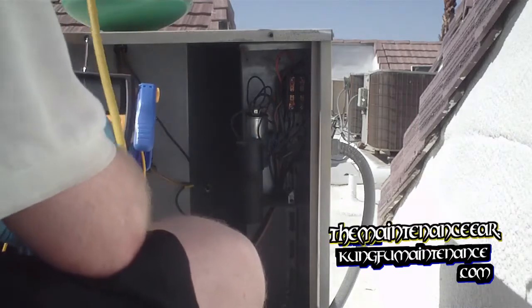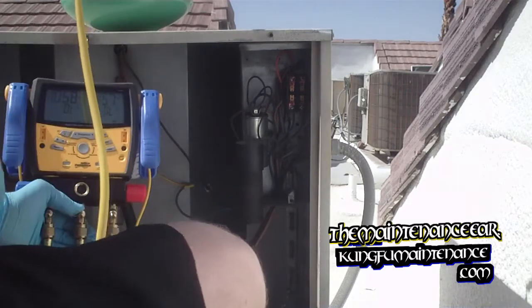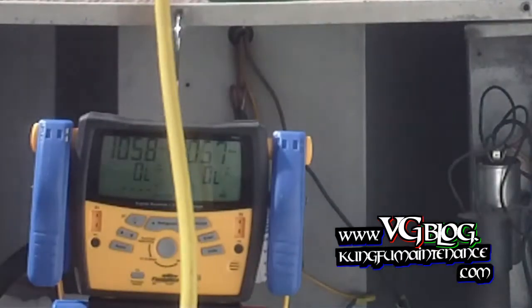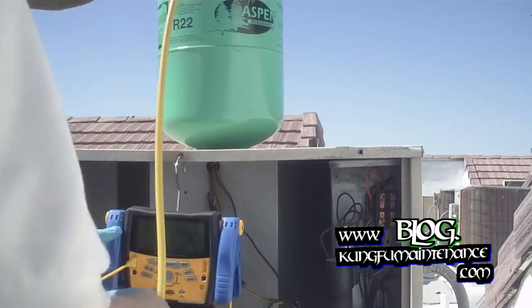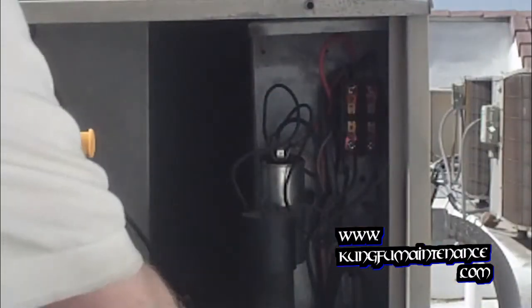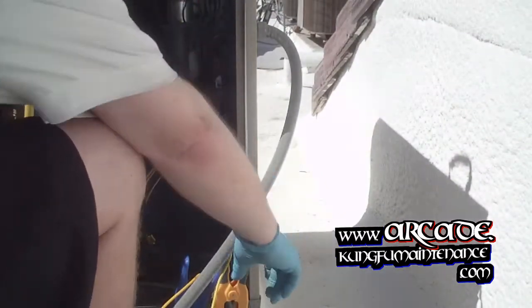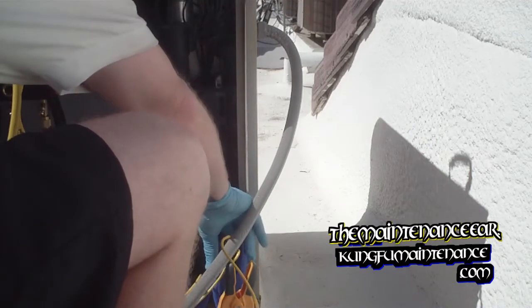Now we're ready to turn it on. Hold it down for a second and turn it on here. Now we've got our K-type clamps on each side, so we'll plug those in — one for our low side, two for our high side. The high side will be clamping on to the high side down lower, and the low side will clamp on down lower. I also have my Fieldpiece meter here with a temperature probe. A little bit overkill to have two of them going, but I'll hook this up right behind it.